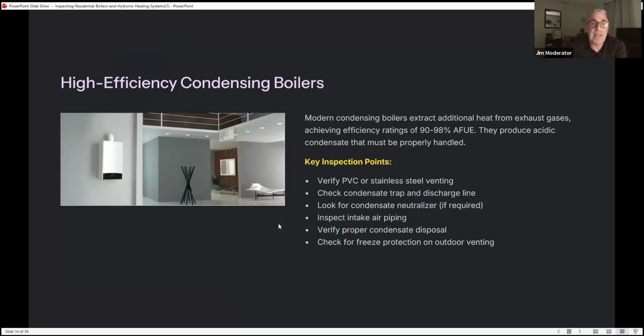High efficiency condensing boilers. Modern condensing boilers extract additional heat from exhaust gases, achieving efficiency ratings of around 90 to 98%. They produce acidic condensate that must be properly handled. Key inspection points: verify PVC or stainless steel venting, check condensate traps and discharge lines, look for condensate neutralizer if required, inspect intake air piping, verify proper condensate disposal, check for freeze protection on outdoor venting. So that's a little checklist there.